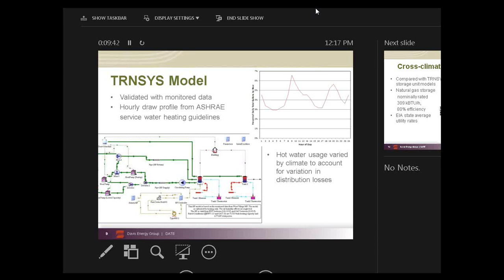So the TRNSYS model using the monitoring performance map was developed to ultimately perform a full year simulation and then run in various climates. The model is structured very similar to the plumbing structure of the system, but different heat pump water heater models were used to simulate both startup conditions in which the capacity is degraded, freezing lockout in which the compressor would be shut off, in this case it was 32 degrees, and evaporator fan modulation that was observed at high outdoor ambient conditions.